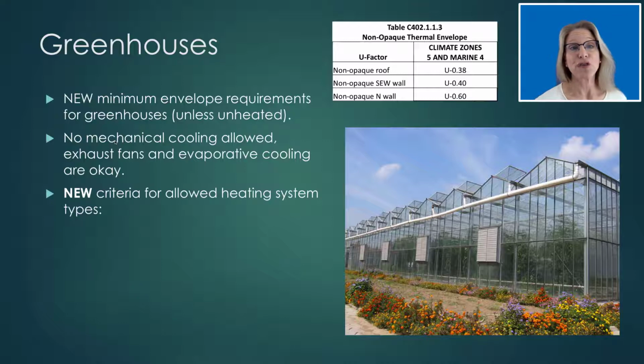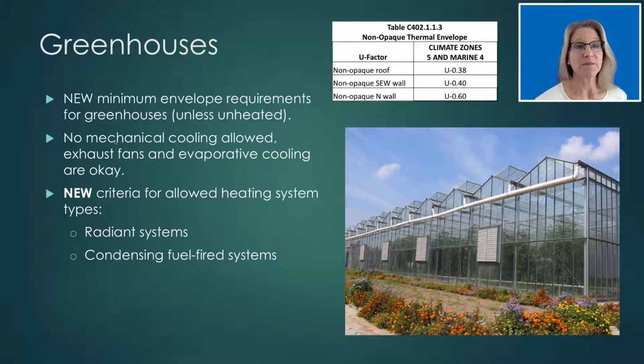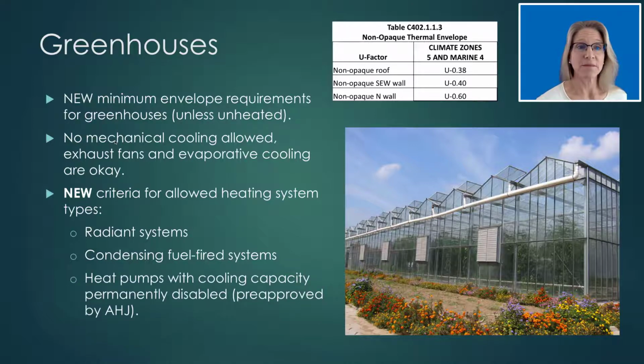And there is now new criteria for the types of heating systems that can be used in a greenhouse. In the previous codes, there were no guidelines about the types of heating system that could be installed. So this is a new criteria for this building type. You can install radiant systems, condensing fuel-fired systems, or heat pumps with the cooling capacity permanently disabled. So same thing as semi-heated, and you do need to make sure that you get pre-approval by the jurisdiction ahead of time.